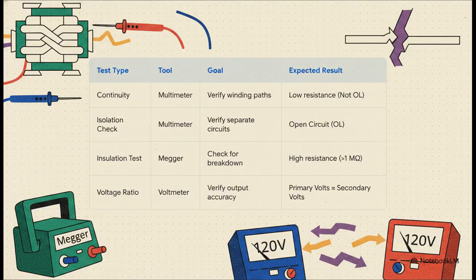And this little chart is basically your pre-flight checklist. You use a multimeter to make sure the coils aren't broken. Then, crucially, you check that the input and output are actually isolated. Your meter should read open circuit. After that, you'd use a special insulation tester called a Megger to make sure the insulation can handle high voltage without breaking down. And finally, a quick voltage check to make sure that 1-to-1 ratio is holding steady.